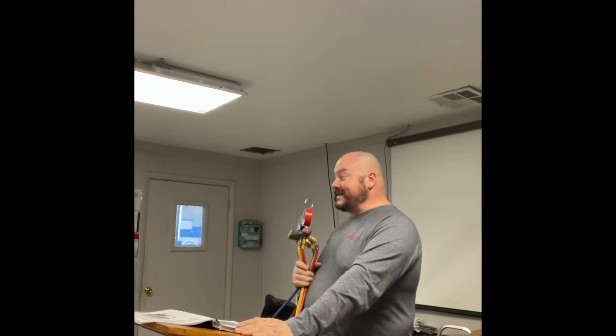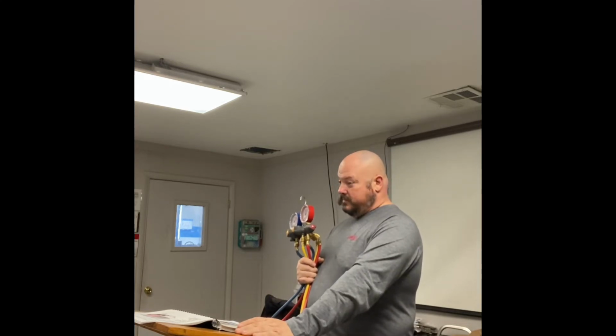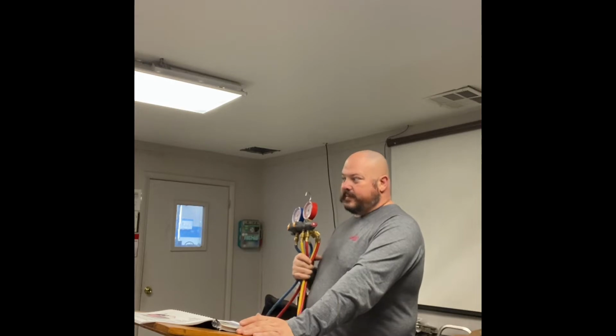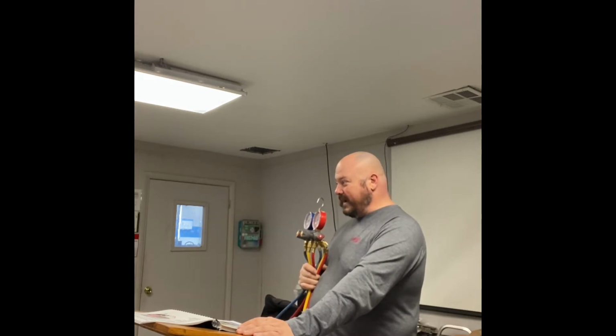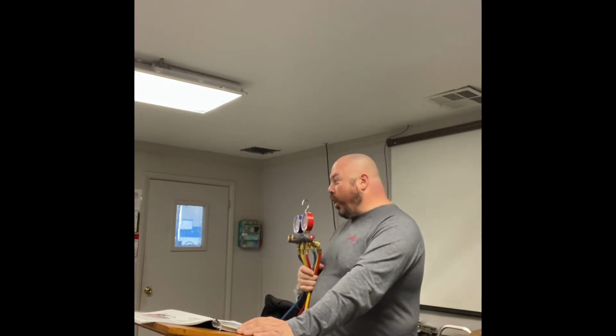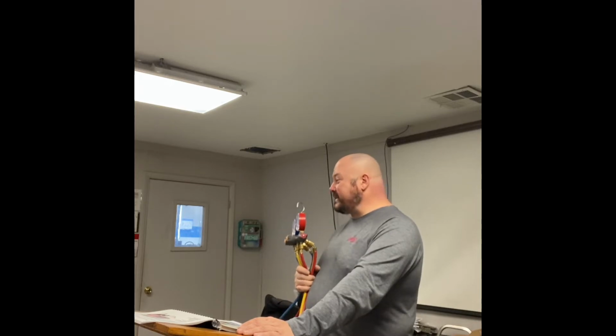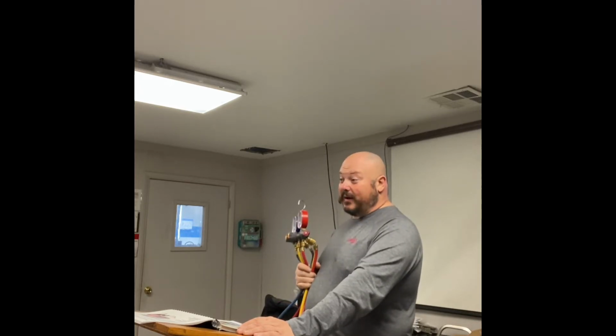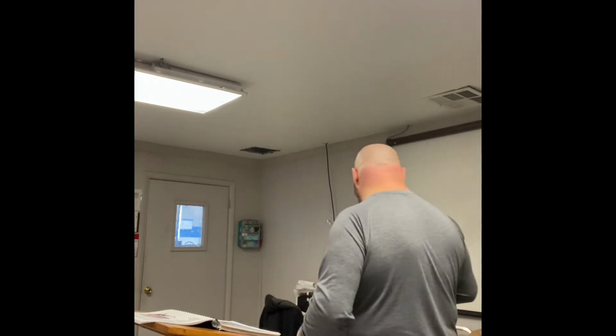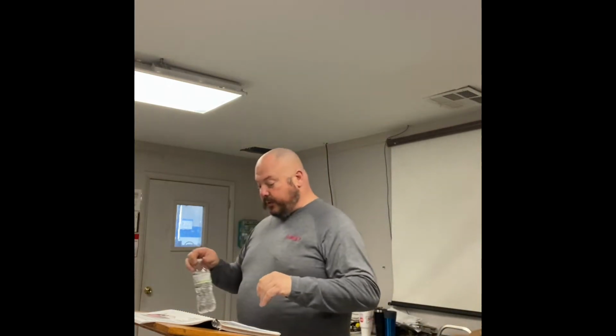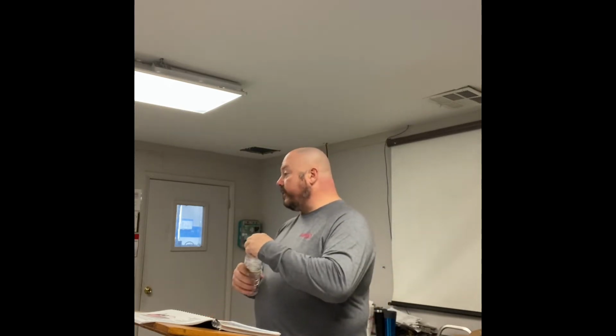But you should hear a serious hissing sound. That's definitely not 250 psi. You guys have heard me shoot the little cannon out, the dart gun, at 300 psi with a 3/4 inch hole. You know, that's a serious sound. You're going to hear it. A deaf guy like me can hear it. So, the answer is pretty much immediately you're going to know, but give it a couple minutes and you'll be able to find out. Your gauges, like I said, will tell you which side it's on.